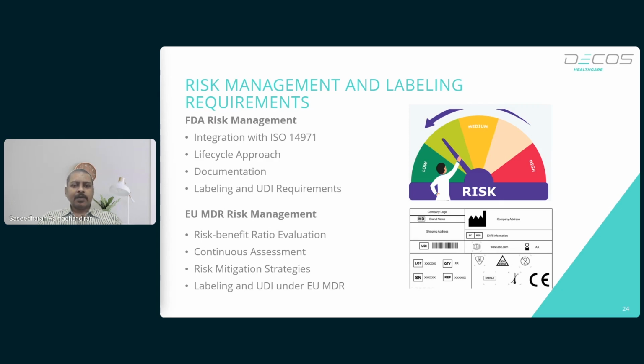Coming to EU MDR's risk management, like FDA, ISO 14971 is utilized across the entire life cycle of the device to recognize and mitigate risk. EU MDR emphasizes the risk-benefit ratio evaluation, where manufacturers must regularly assess whether the benefit of the device continues to outweigh the risk. Measures are implemented to minimize risk as a part of a comprehensive risk management strategy.